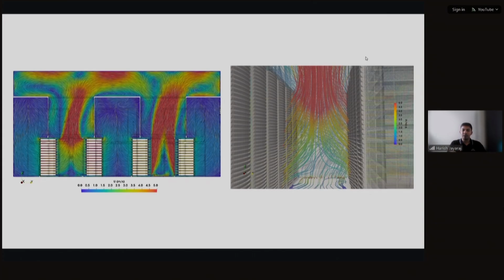After it moves up, we have to provide a proper ventilation or exhaust system so the heat goes out evenly. If it's too abrupt, we won't get proper airflow — it has to be slow, and there's a concept called residence time. Even if the air is moving very fast, it won't transport much heat; it just consumes a lot of energy moving air around. So we have to check whether the residence time is proper, so convection has time to let the air take in the maximum amount of heat before it goes out, so the processor cools efficiently. This is another situation where we have to look at data, not just visualization.